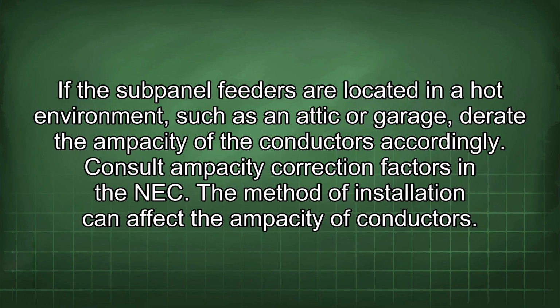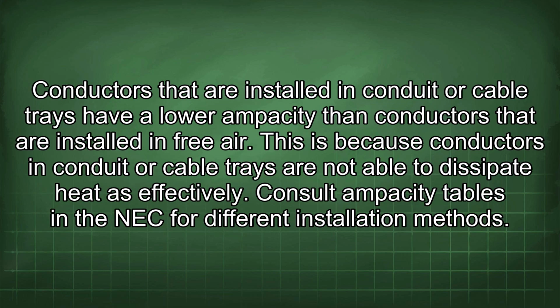The method of installation can affect the ampacity of conductors. Conductors that are installed in conduit or cable trays have a lower ampacity than conductors that are installed in free air. This is because conductors in conduit or cable trays are not able to dissipate heat as effectively. Consult ampacity tables in the NEC for different installation methods.